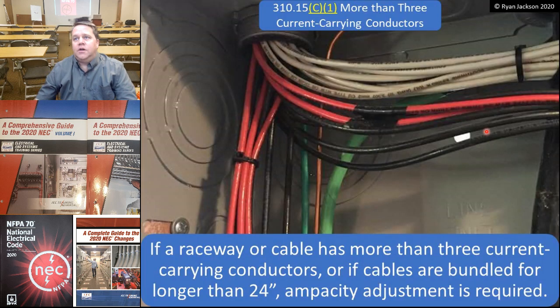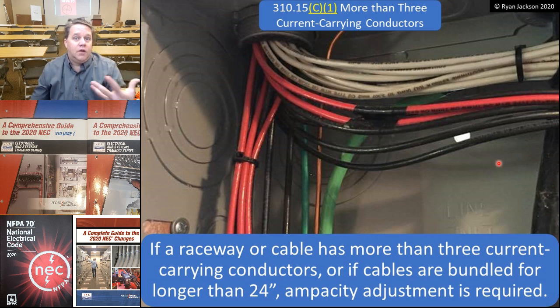When do you count a current carrying conductor? Well, I guess we should start by saying why you need to know what a current carrying conductor is, and that's in 310.15C1, or again, what used to be 310.15B3A. It starts out by saying if a raceway or cable has more than 3 current carrying conductors, or if cables are bundled for longer than 24 inches, ampacity adjustment is required.